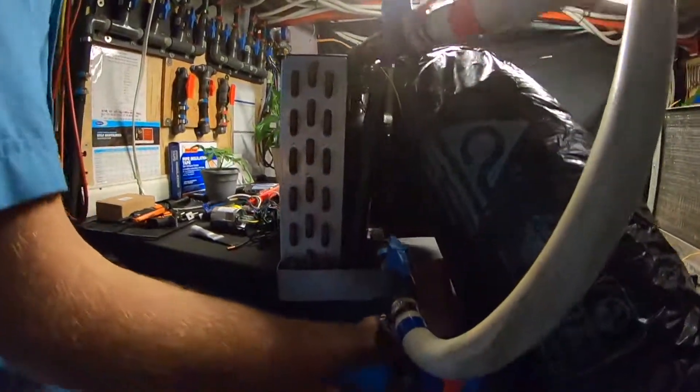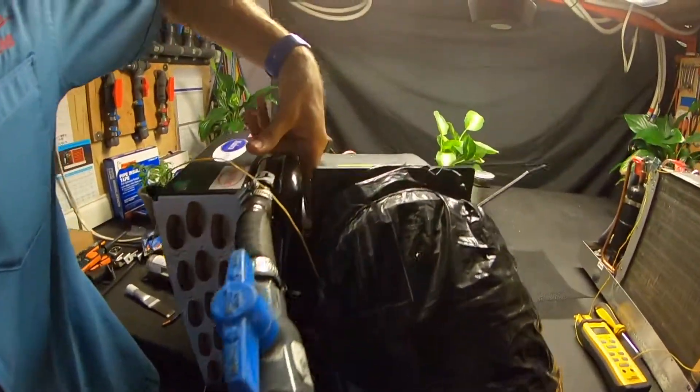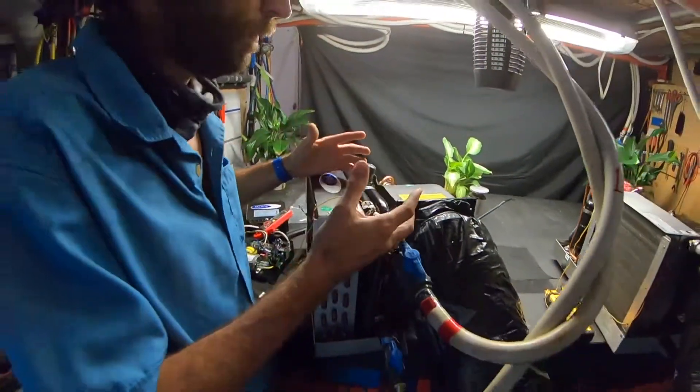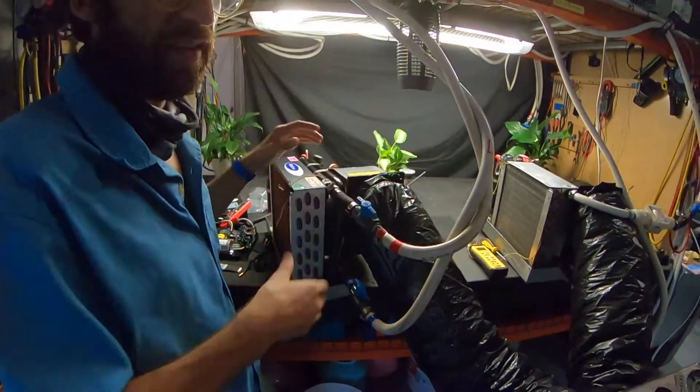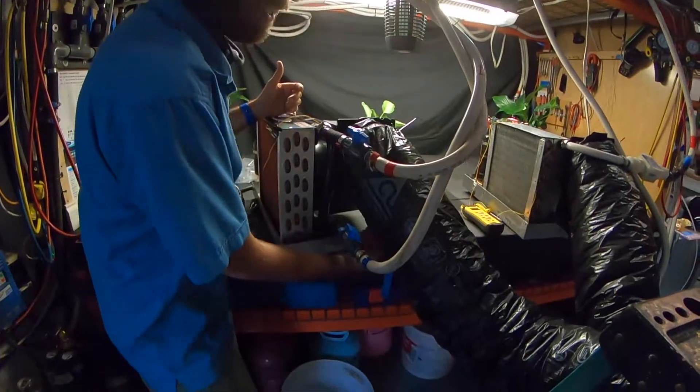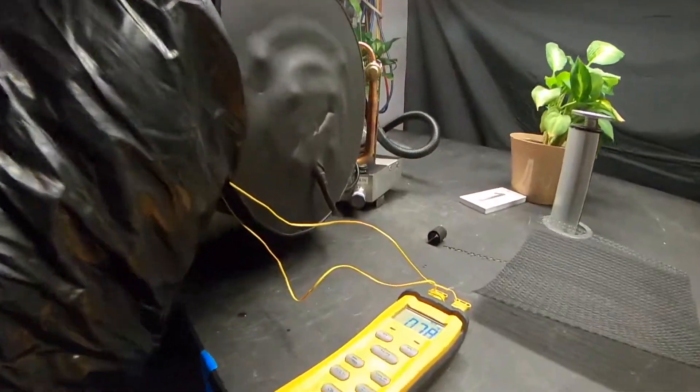Apart from that, you'll see the pan. We were talking about the blower being able to rotate. Another benefit to this pan here is due to this narrow width, if we have an issue, very tight spot to fit the unit into, what we can do is the blower is removable. So you remove that screw, loosen that clamp, the whole blower comes off. You can fit the unit in where you need it to go. You can mount the blower back in the area once it's installed in its location. It makes it a bit easier to install the unit without having this piece because you're fitting in an L shape versus a rectangle.